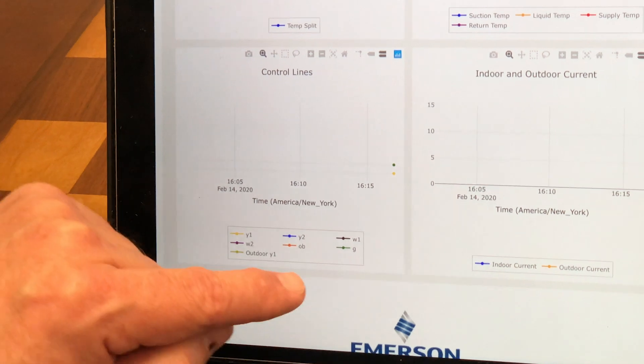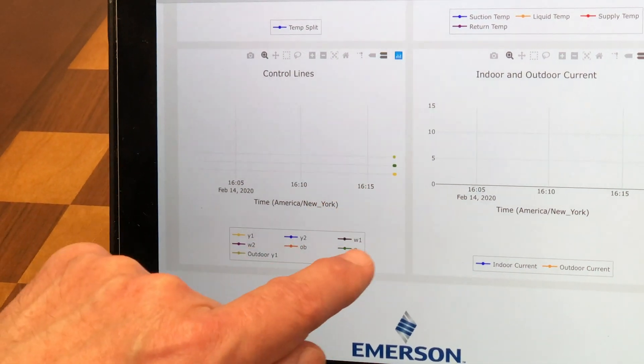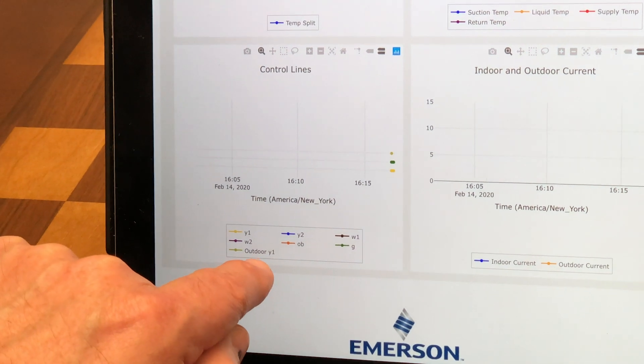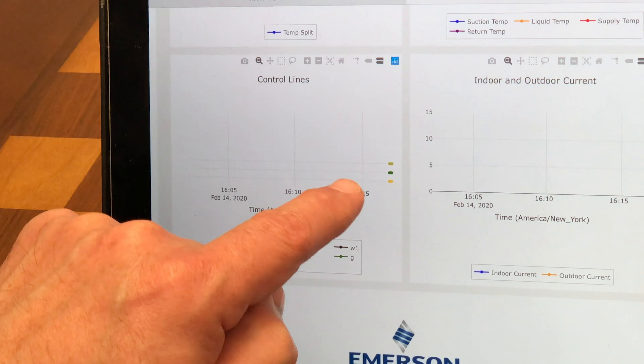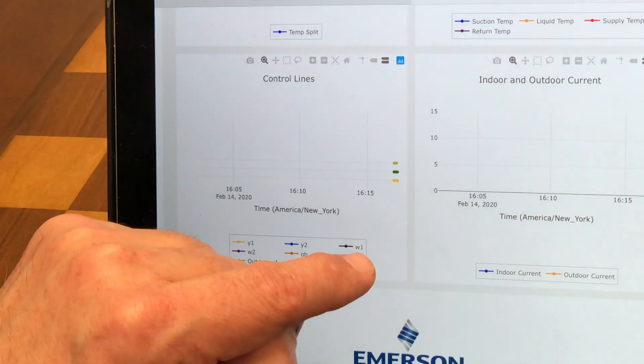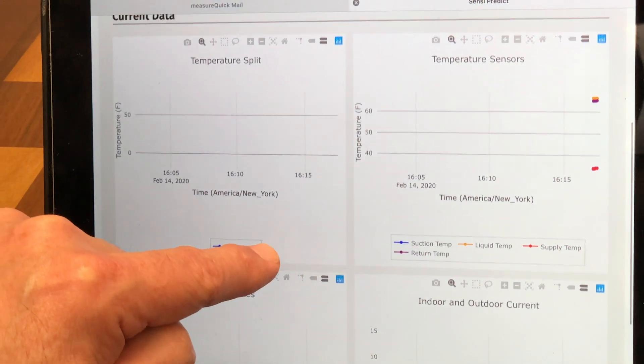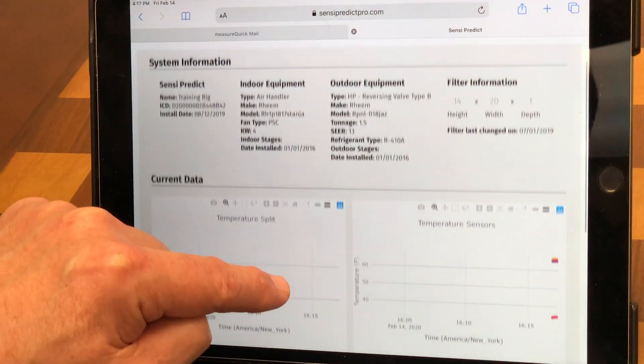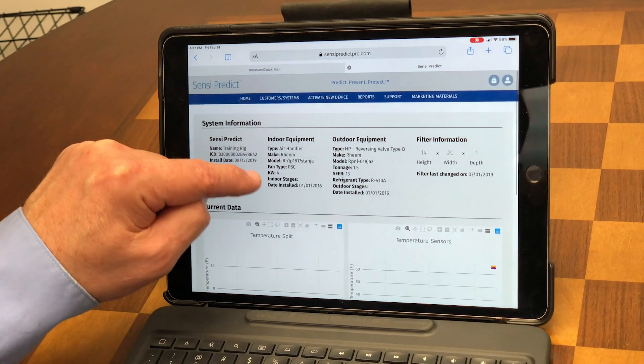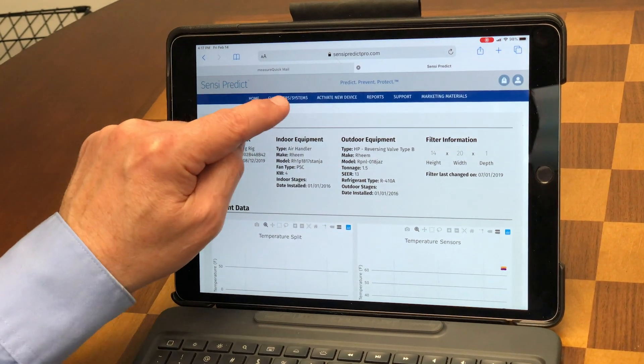You can see I have a call for G, a call for Y, and a call for outdoor Y1 — so everything is calling outside. My inside call is going to my outside, the system is obviously running, and I can see my indoor and outdoor current on here, so all my data is here. This is one way of looking at it, but we can also look at this through MeasureQuick.